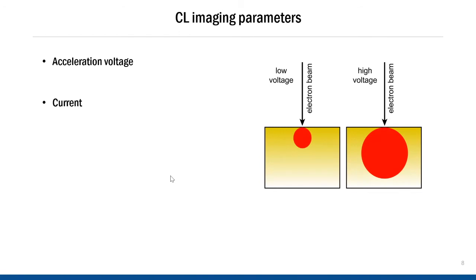Another issue is sample damage or contamination. The combination of high voltage and high current may result in high CL emission, but it may also result in beam induced damage to the sample or contamination or heating or charging. In some materials like semiconductors, for example, the sample can start exhibiting undesirable behavior at high current and voltage. So once again, the right combination of these parameters needs to be found so you can deliver the optimum electron dose to get a good CL signal without damaging the sample. Now, it's important to mention that the balance between these parameters lies at a different point for every material. So it's possible to make some recipes for imaging. For example, you can see that a certain energy and current would result in a good signal for gallium nitride or zircons or phosphors. But these need to be used as guidelines as a place to start, and then you need to optimize the beam energy and current for the given sample.